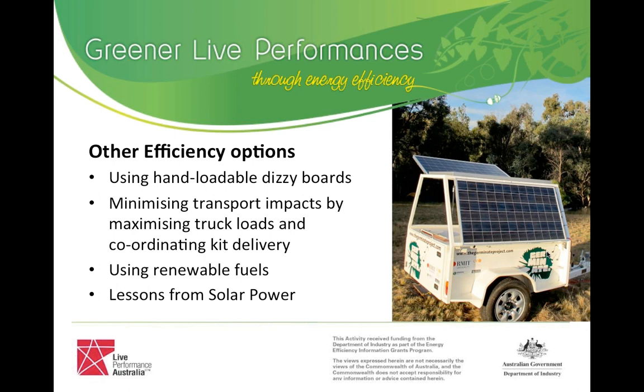If you take the load off your generator at the end of the day and just let it sit there with nothing on it, there's a certain amount of fuel that will still be burnt just to keep that machine operating at 1500 RPM, but nowhere near what it would be under load conditions. So there is a baseline amount of fuel that's going to be consumed — almost an idling scenario — and it will use more fuel for more power output as demand grows. In that way it is responding to your power demand, but you've got a baseline fuel consumption whether power is being pulled or not.